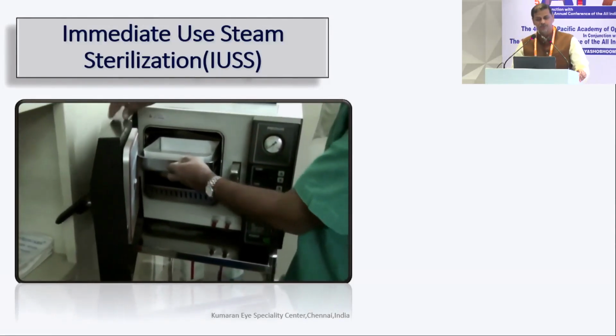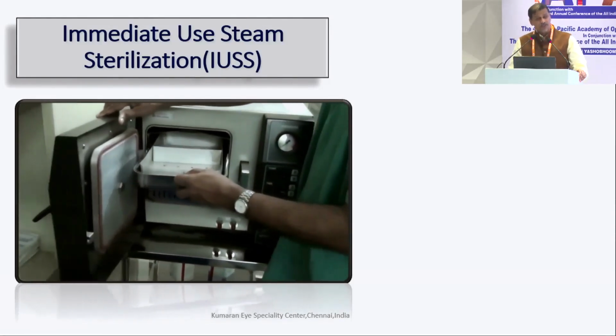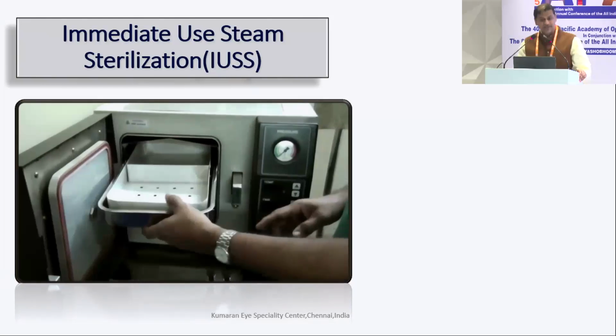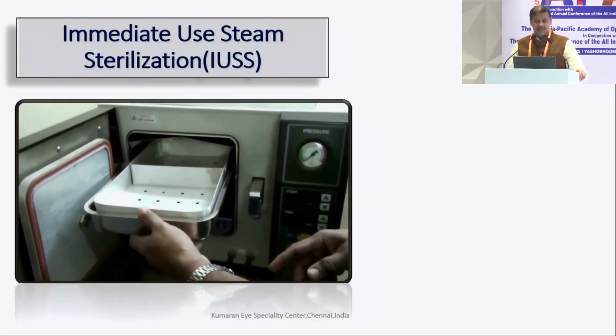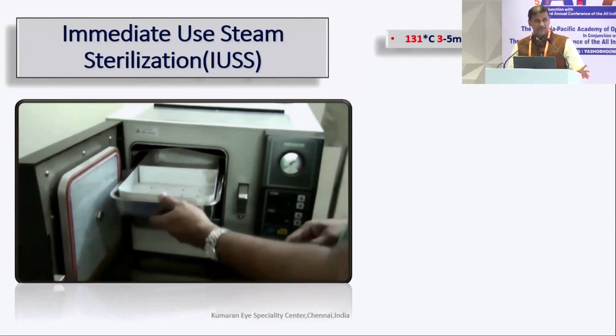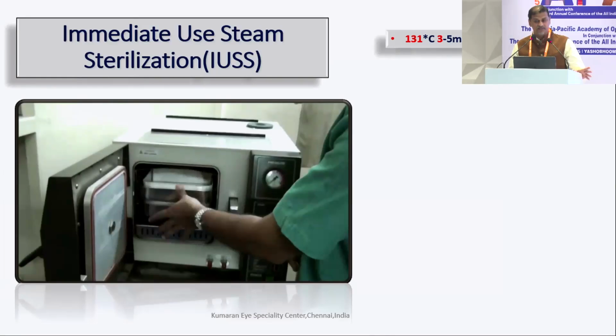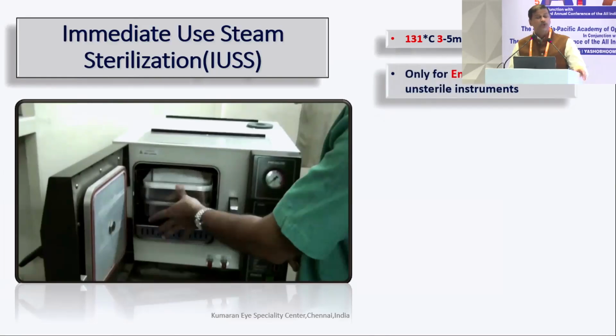So as I told you, this is a newer term for flash sterilization. It's called immediate use steam sterilization. It has a role in ophthalmology. The temperature used for this is 131 degrees Celsius for 5 minutes. There's a rapid increase in temperature, so it's used only for emergency use.